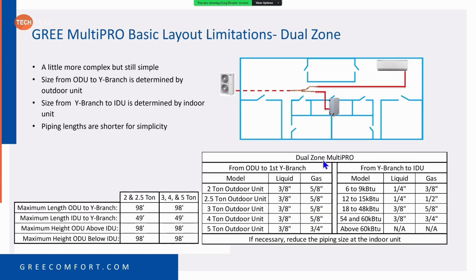So, GREE MultiPRO basic layout limitations in a dual zone. A little more complex, but still simple. Size of your outdoor unit, the Y branch is determined by the outdoor unit. So this dotted line right here is going to be sized by the outdoor unit, as we talked about a minute ago. So if I'm doing a 4 ton, it's going to be 3/8, 5/8. If I'm doing a 5 ton, it's going to be 3/8, 3/4. Size of the Y branch to the indoor unit is determined by the indoor unit.